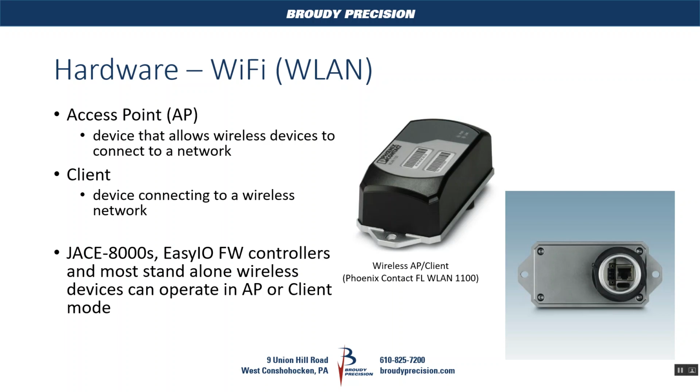With the devices that we see in the HVAC world, like a Jace 8000, an EasyIO FW controller, or something like this Phoenix Contact FL WLAN device here, they can both operate in either an access point or a client mode. So they can broadcast a signal to allow devices to connect to them, or they can connect to an existing wireless network that's out in the field.